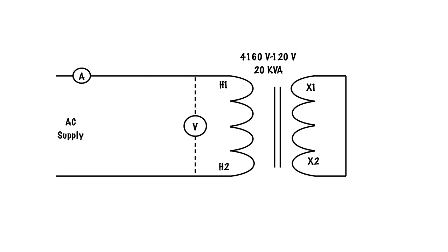And percent impedance is very important to us as electricians because that's what determines how we parallel our transformers. Remember, the three rules for paralleling are that you have to have the same voltage rating, you have to have the same polarities, and you have to have the same percent impedance. So we're going to show how that's calculated, using what's called the short circuit test.